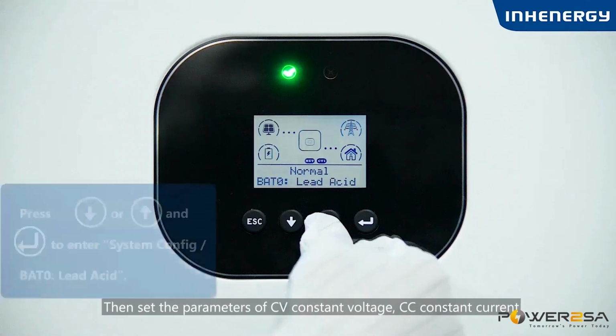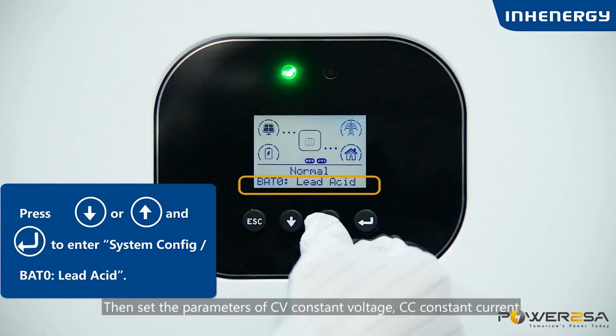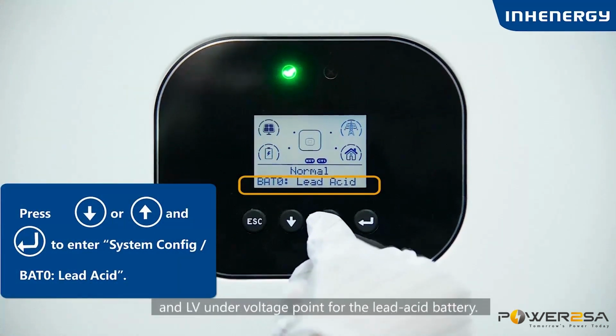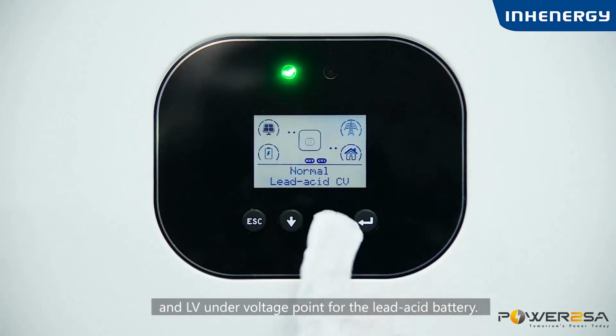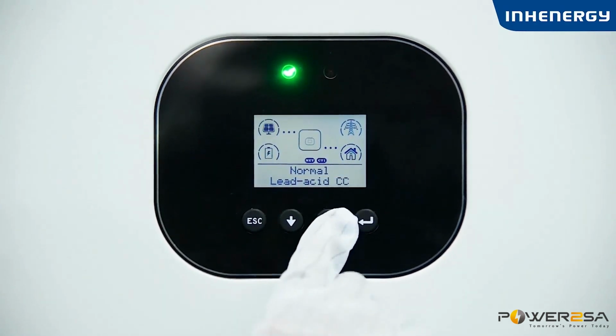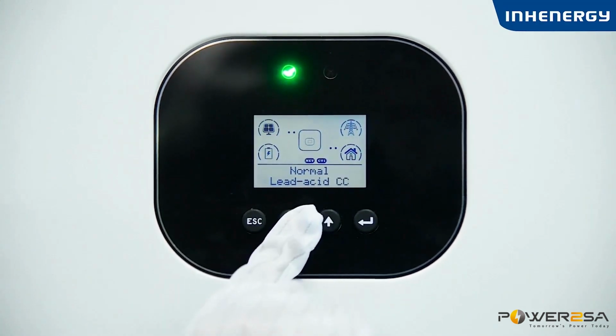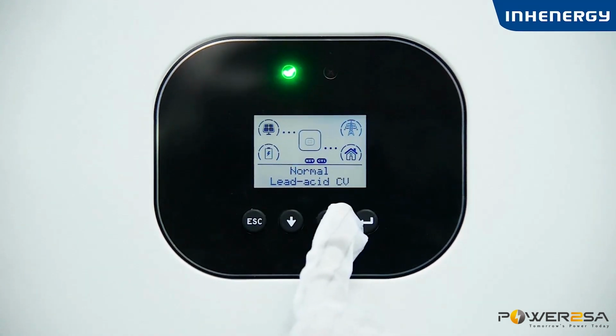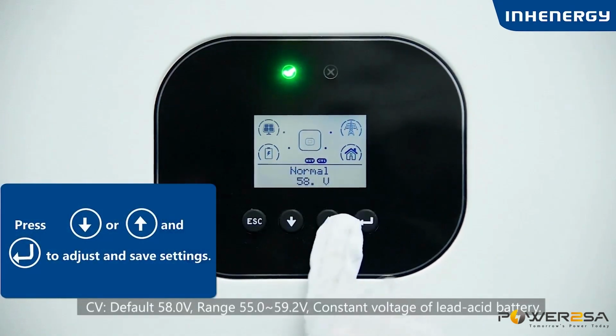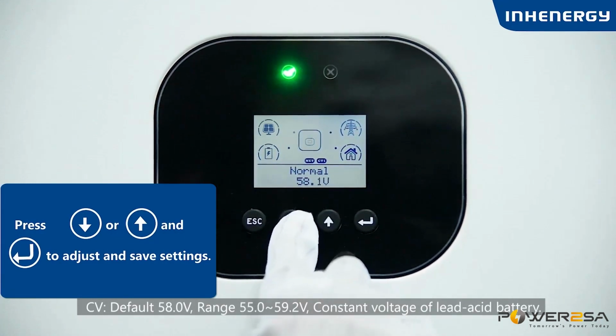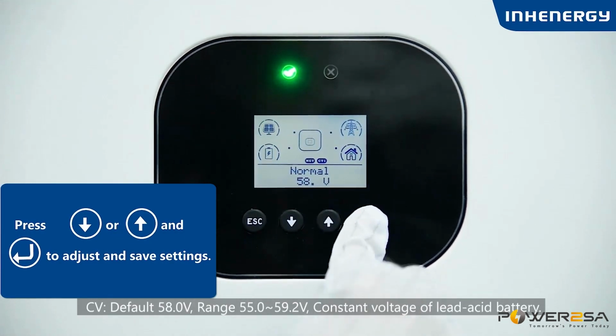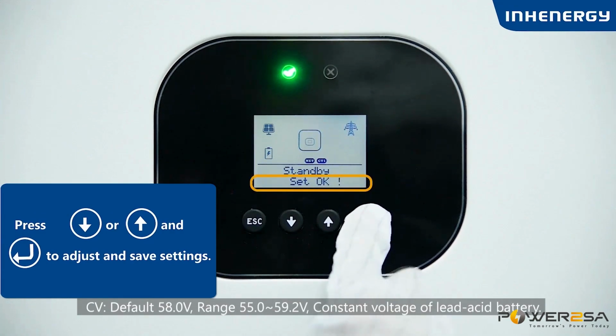Then set the parameters of CV constant voltage, CC constant current, and the LV under voltage point for the lead-acid battery. CV default 58 volts, range 55 to 59.2 volts, constant voltage of lead-acid battery.